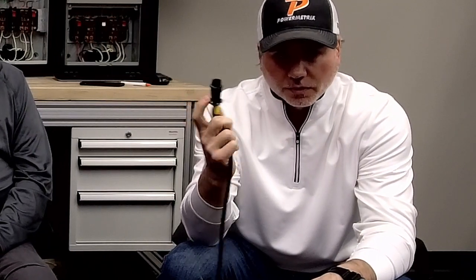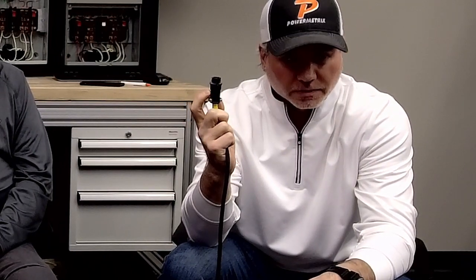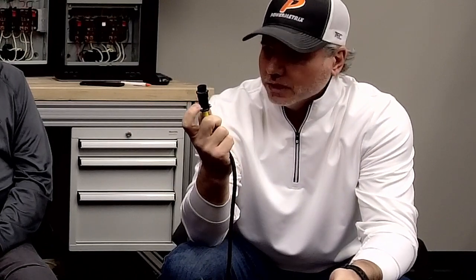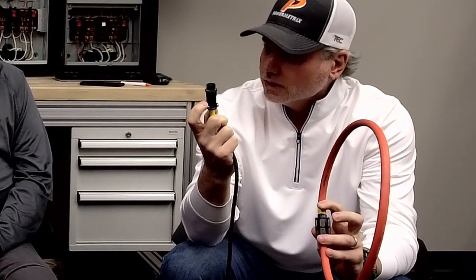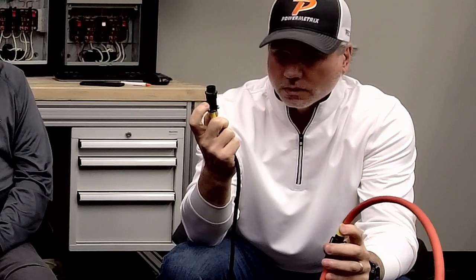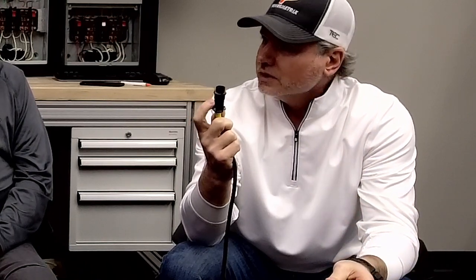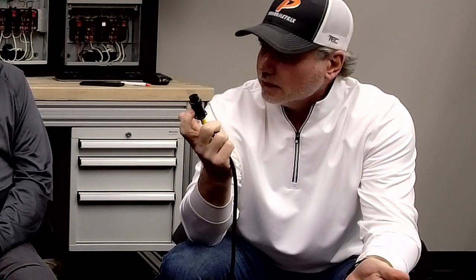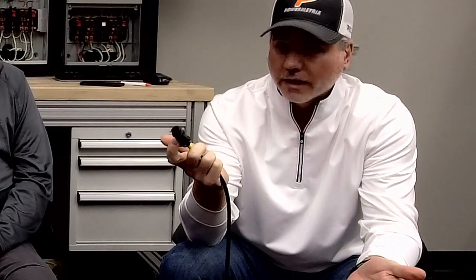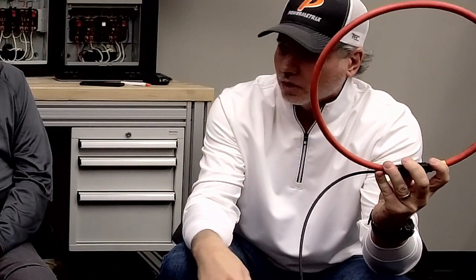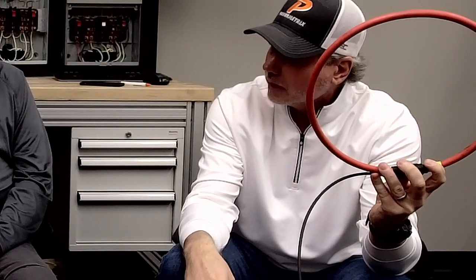So let's talk a little bit about flex probe theory, or any of our probes for that matter. The connection point here goes to the probe adapter cable, and that's where we have our communication chip in there. So in that chip is what type of probe this is, what's its serial number, and also what are its calibration values. We calibrate these in-house, as everyone knows, so you get the best field accuracy as possible. Off the shelf, any of these Rogowski coils are probably about a 1% probe.